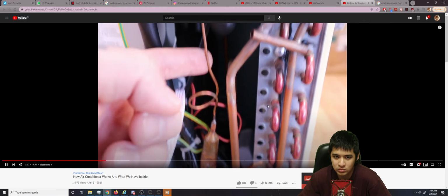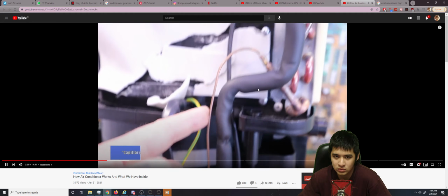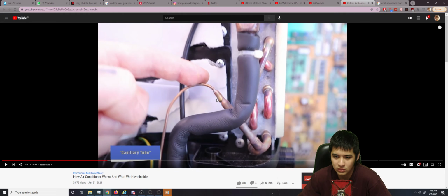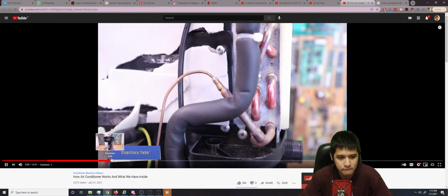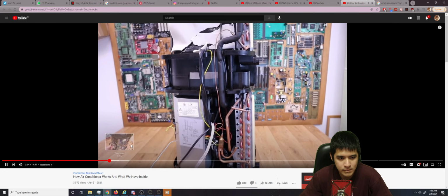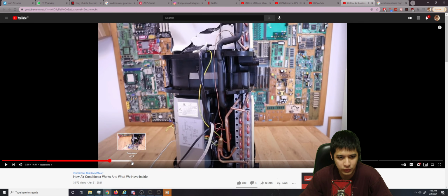Actually, this setup is using an expansion valve that is based on a capillary tube. Again, metering device, not an expansion valve based on capillary tube. TXV is a metering device, as well as capillary tube, which is just a long copper tube with a very small internal diameter. Okay, let's skip. If you want to check the full video, go ahead on his channel. I won't play the whole video here.